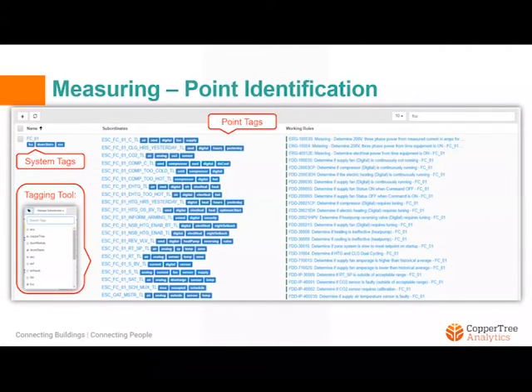Point identification. In regards to this topic, how many of you have been frustrated with a BAS point naming convention or lack of a standardized naming convention? Using tags is a way to solve this problem while also providing many other advantages. Shown here is a fan coil unit with all corresponding sensor and control points, all tagged using a combination of Haystack and custom tags. You can see the equipment name, FC_01, in the top left, which has 3 system tags applied to it. And just to the right of that, you'll see all of its subordinates, which are the fan coil unit equipment points. These control points are all assigned tags using our tagging tool, which allows us to quickly streamline this process.